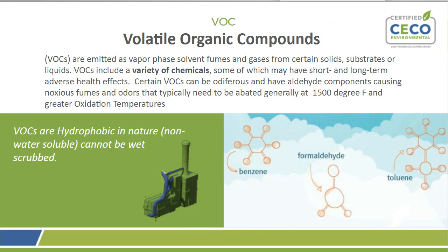For VOCs, we'll go through just a couple of real quick definitions here. The volatile organic compounds, or VOCs, as we refer to them, are typically solvent fumes and vapor phase gases. They contain carbon. They can have acids in them. And a lot of these will have aldehyde type components, the longer chain hydrocarbons, and they cause noxious and toxic fumes and smelly odors. And typically these need to be broken down, abated, oxidized, or incinerated at around 1400 to 1500 degrees Fahrenheit and greater on thermal oxidizer technologies.